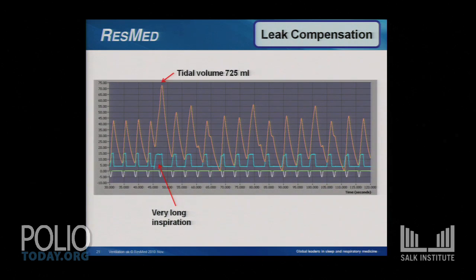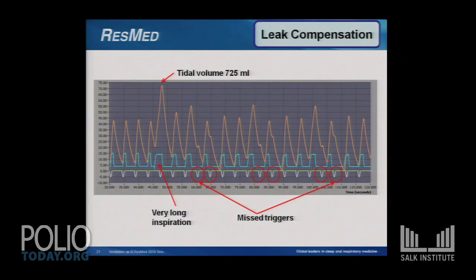Now just for fun, I wanted to show you a competitive product, exact same test, exact same settings. Here I created a leak right here. And you can see this super long inspiration because of that leak. This is on that competitive product. You can see the tidal volume on that breath shot way up. It's enormous. But what's especially important is look how long it took. That ventilator did not get back in synchrony. Here's a patient effort, but there's no breath right there. Here's a patient effort, too late. Here's a patient effort, no breath. Patient effort, no breath. So some machines, if they don't have good leak compensation, don't stay in synchrony with the patient. And that's probably the number one most important feature for a ventilator for you folks that are looking for something to be comfortable and therapeutic. We've got to manage those leaks. That's the most important.